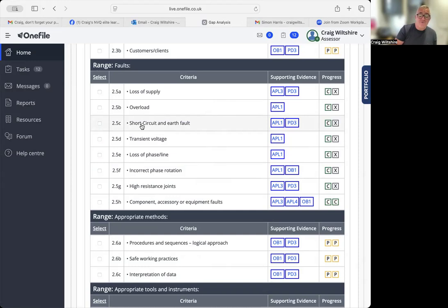I went back to the board and I retested with my insulation resistance tester and yielded a result of greater than 999, which is more than my tester can read. So it's greater than 999 megaohms. And I was satisfied that after retesting, my circuit was then fixed and the fault was now cleared. So I have no longer got an earth fault on that circuit. Okay, that's how I would explain it to me, right?